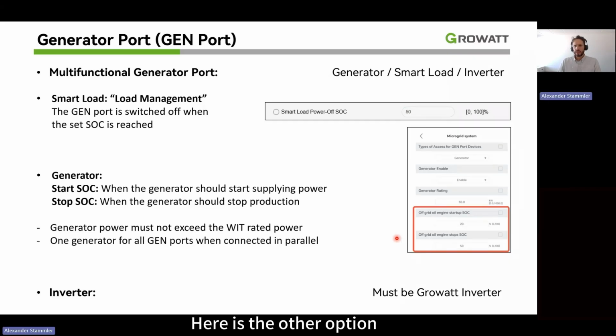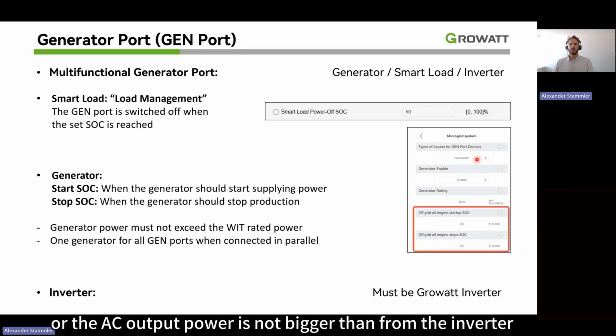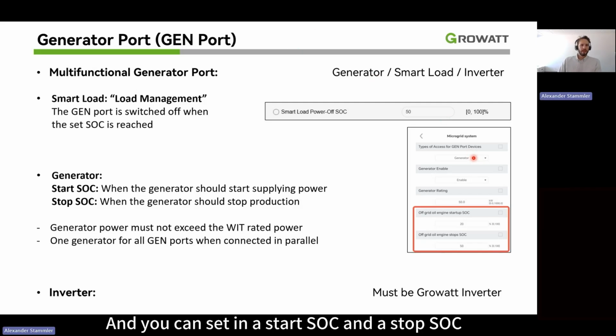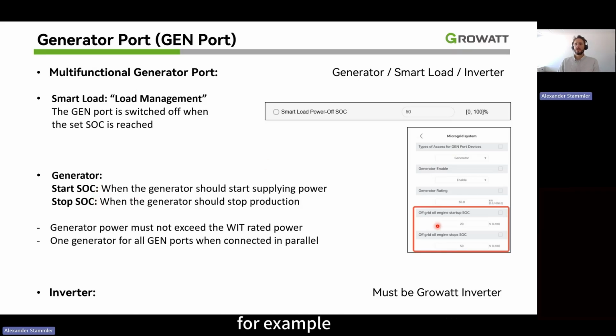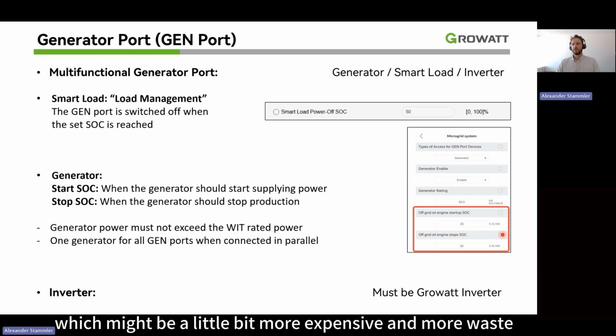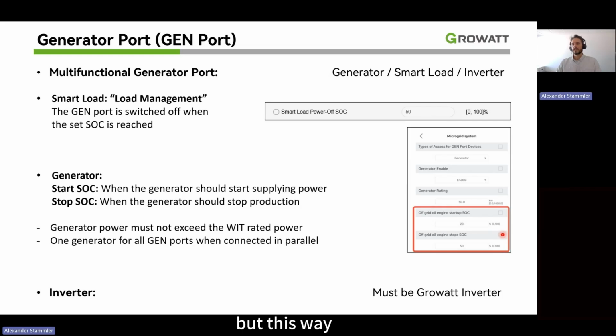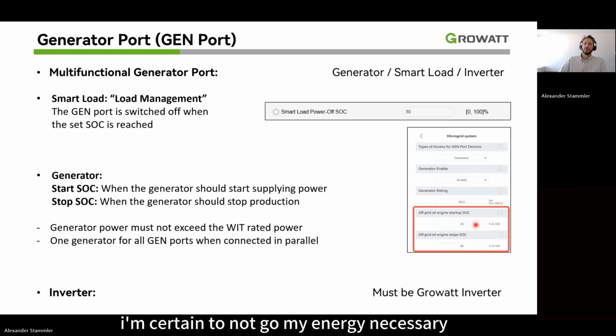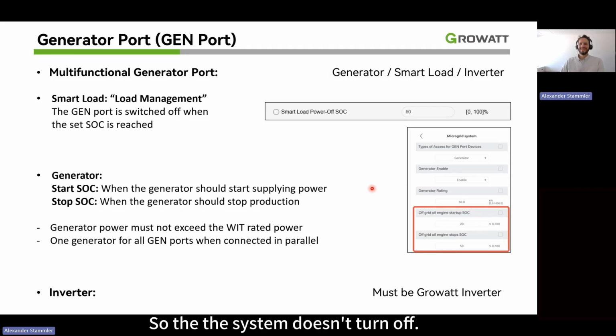Here's the other option. If I use the generator, I can connect a generator, and it is important that its AC output power is not bigger than that of the inverter. And you can set in a start SOC and a stop SOC. For example, when the battery is in off-grid function and at 20%, I want the generator to start and to charge my battery up to 50%. So this way, I'm certain that I will always have power, even if the power is produced by a generator, which might be a little bit more expensive, more waste. But this way, I'm certain to not go below my necessary energy, so that the system doesn't turn off. Yeah, I think it's clear.